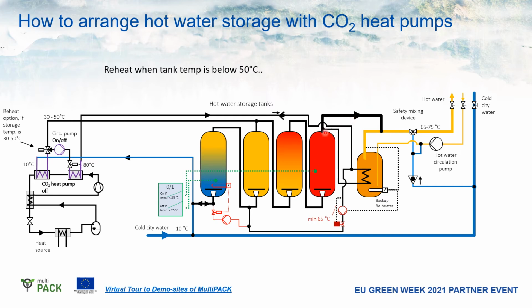The next example is a challenge which might happen if the operating conditions are changing during a day, during a week, or season of the year. Since this water column is going back and forth, heating up and being pushed back, there might be intermediate water in a range of 30 to 40, 50 degrees inside these storage tanks. One way to reheat this would be to divide the gas cooler into two gas coolers.